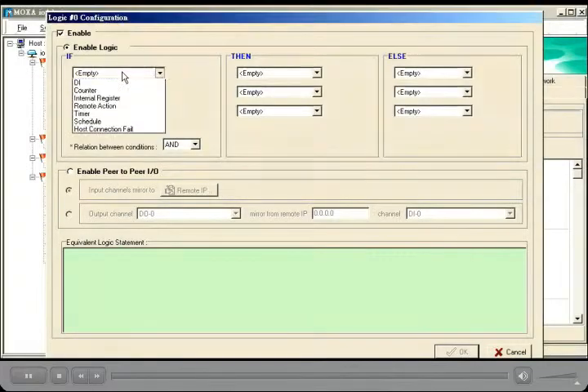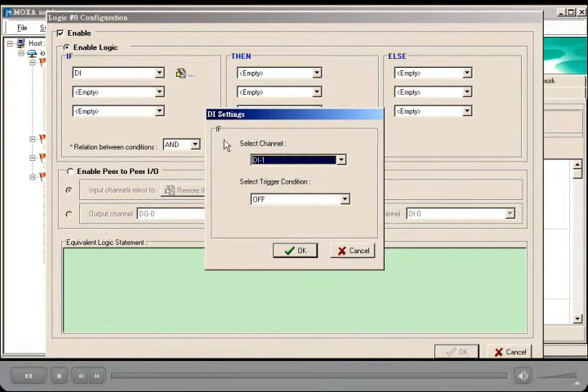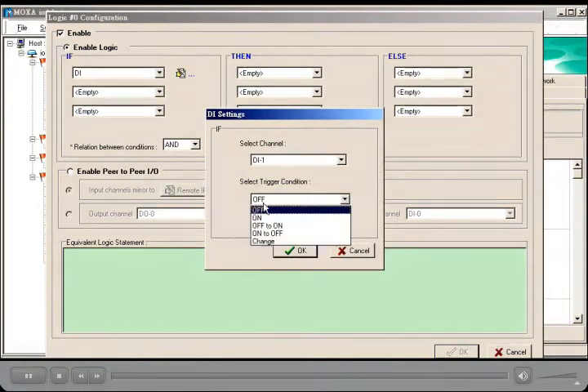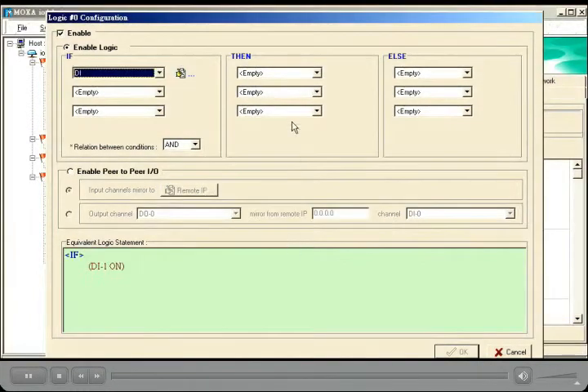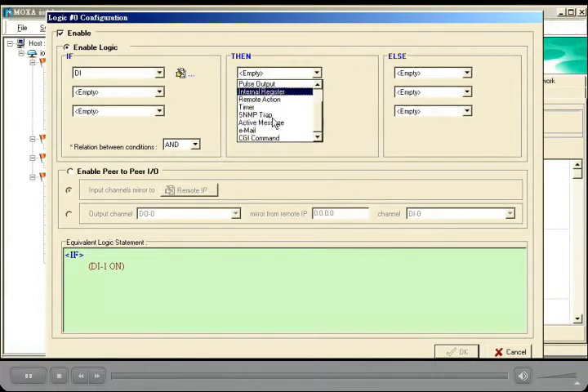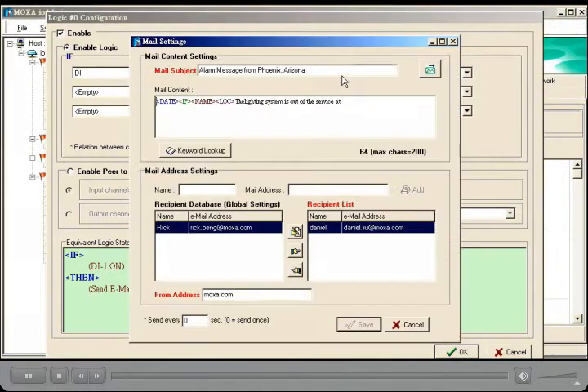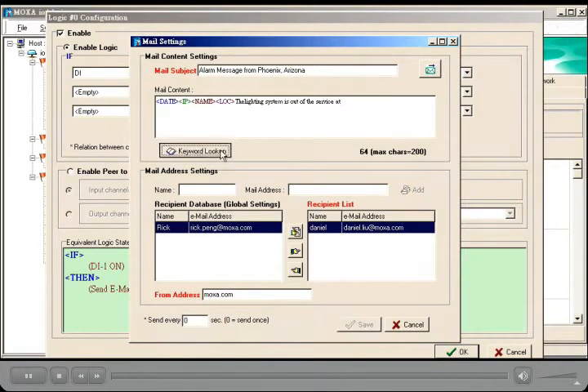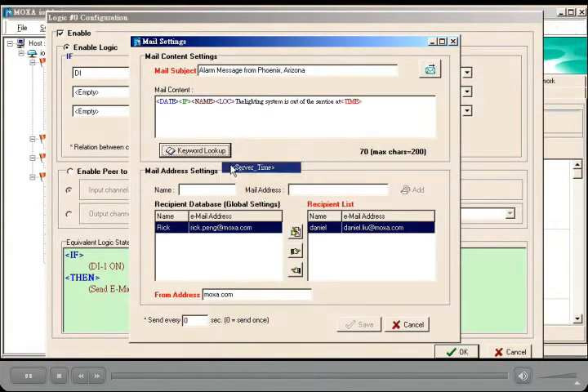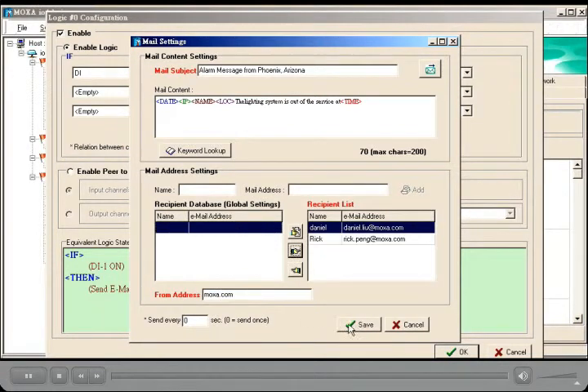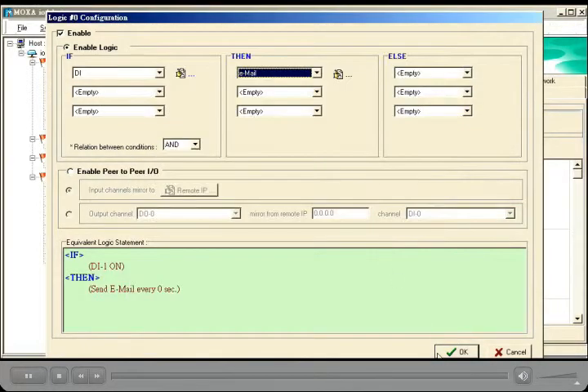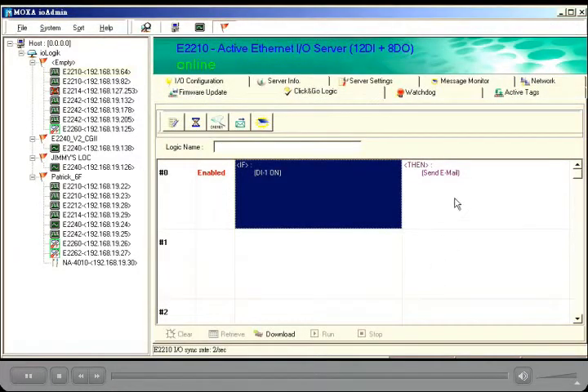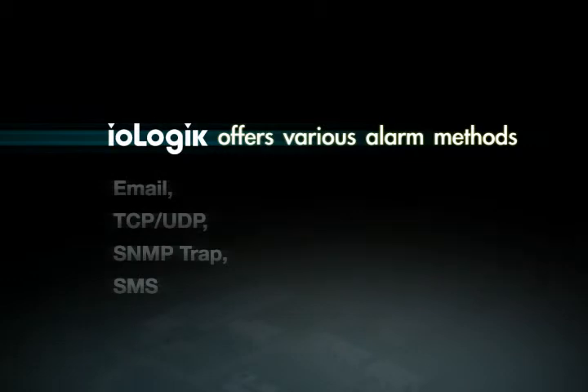Take email alarm notifications, for example. If you wish to set up an email alarm that is triggered by a digital input, all you have to do is click on the DI channel that triggers the email alarm in the IF condition, and then enable the email alarm in the THEN condition. The email content is editable. Simply set up the email recipient's address, server address, and key in the username and password, and the email alarm system is ready to go.